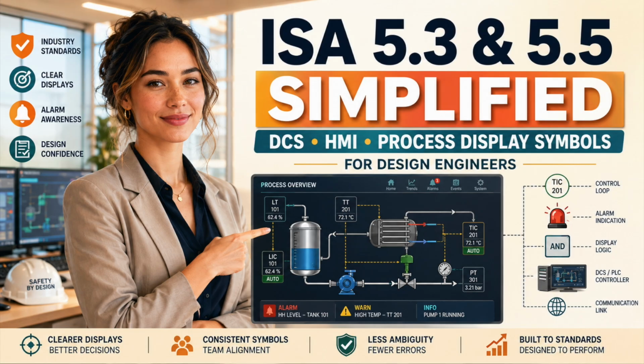The package engineer must prevent supplier-specific conventions from entering the plant uncontrolled. Operations must validate whether the screen supports startup, shutdown, upset response, and troubleshooting. Maintenance must challenge the design with failed feedback, bad transmitters, communication loss, local operation, bypasses, forced values, and device replacement. This is not work that should be postponed until the end of configuration.